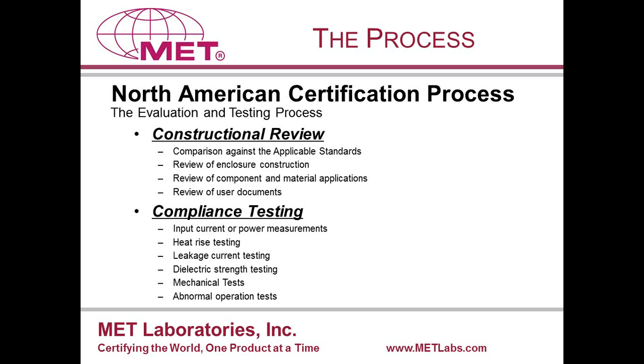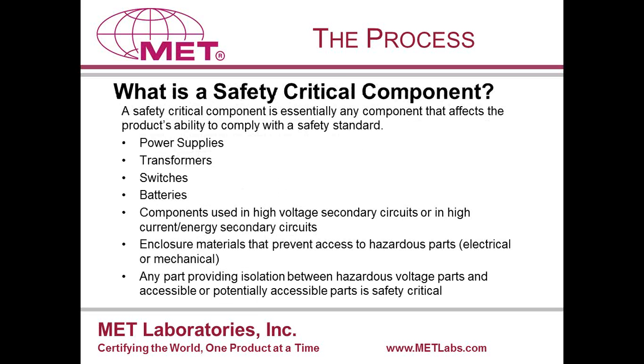One very important product of the evaluation is a table called the List of Safety Critical Components. A safety critical component is one that the engineer has identified as impacting that product's ability to meet the requirements of the safety standard. It might be the flammability rating on the enclosure.